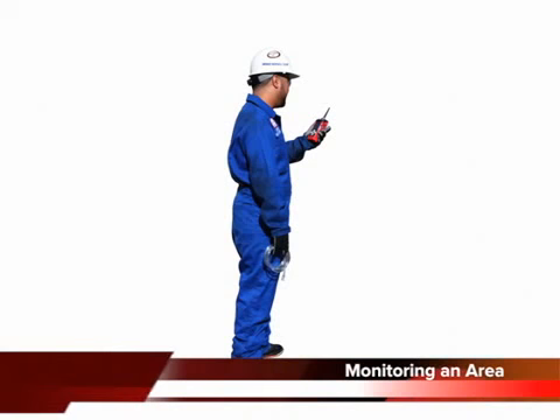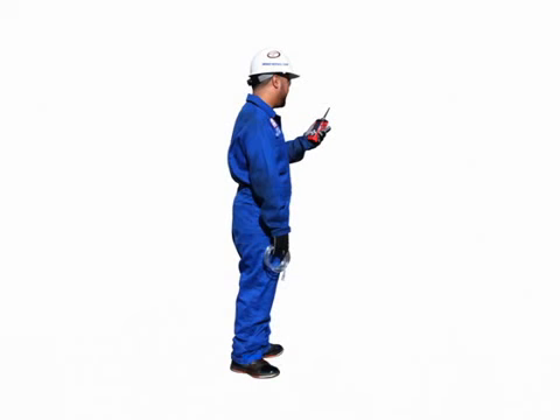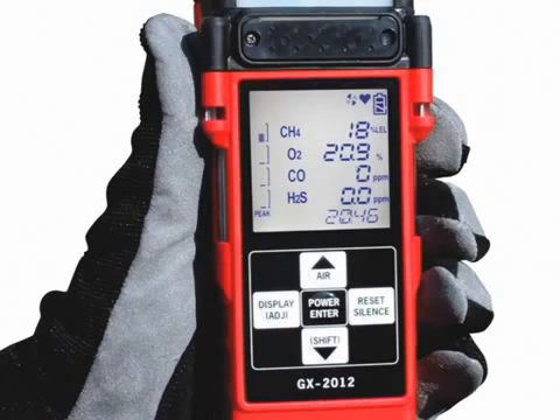Take the GX 2012 to the monitoring area. If the tapered rubber nozzle is used, put the nozzle tip in the area to be monitored. If the hose and probe is used, put the probe tip in the area to be monitored. Wait 10 to 15 seconds and observe the display for gas readings. If a reading is observed, allow the reading to stabilize to determine the gas concentrations present.